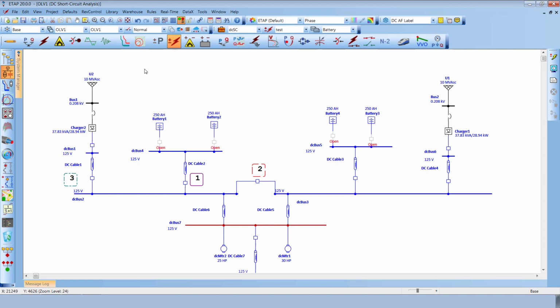This example also includes the calculation of incident energy per stage until the last protective device has completely cleared, and then continue with the modeling strategy plus the scenarios that are used in this project, and then determine the arc flash incident energy result at DC bus 2. The modeling of DC chargers in ETAP 20.